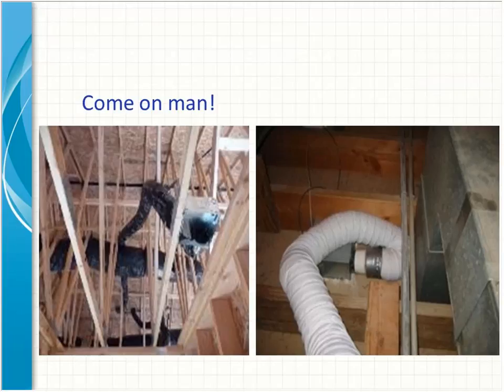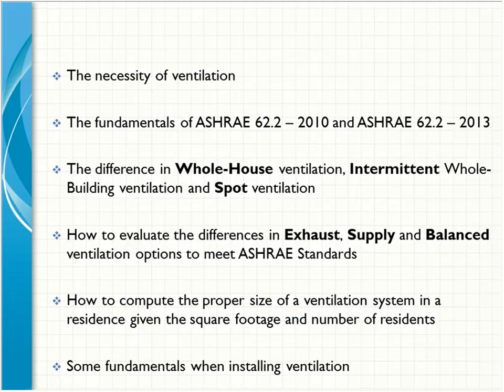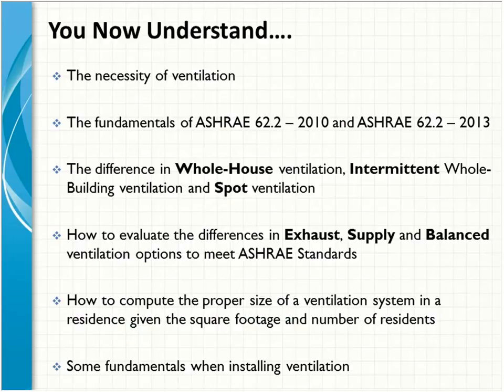But really, if you see this type of install when you're inspecting homes, you know right away. We've got flex duct being used here, which is fine. That's the most common install. But let's at least point the fan in the direction of the termination. The one on the right here, where we come off of the fan and we immediately do 1, 2, 3, 4 90-degree turns with flex duct before we're a foot away from the fan, is absolutely a terrible install. So we want to be looking for these types of things and helping our ventilation equipment do the job that we designed it for.